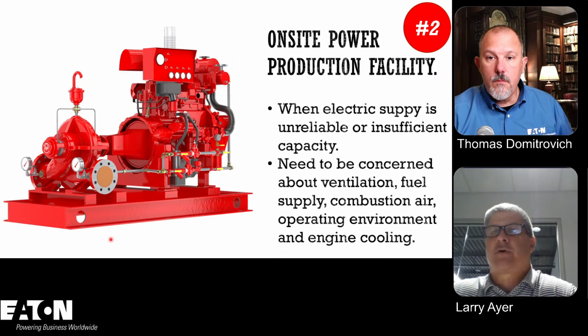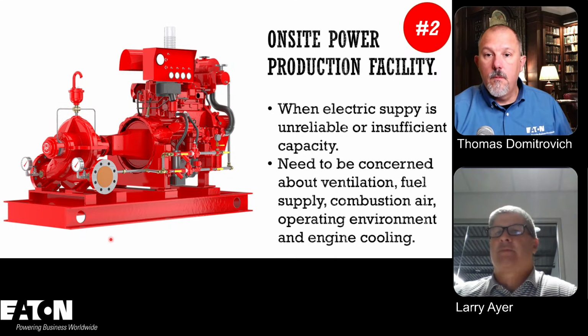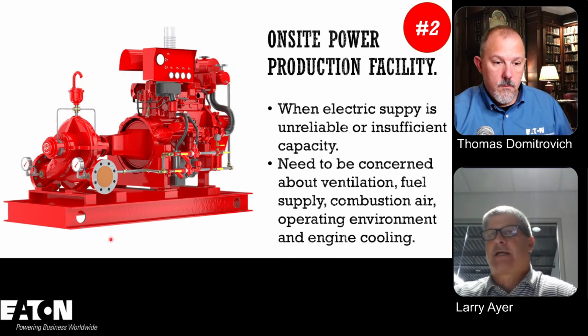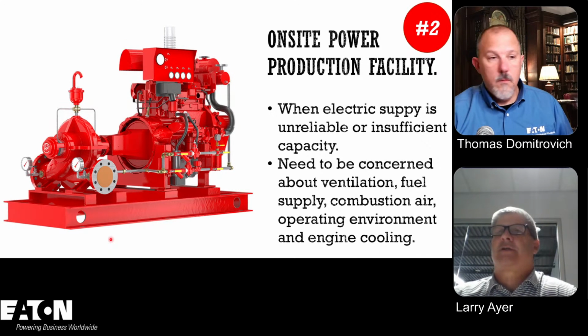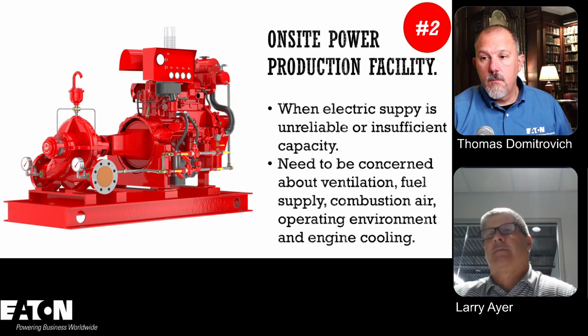You don't need to worry about whether you need another source of power, but you do need to be concerned about ventilation, fuel supply, and combustion air. Like I think Don said before, if it's outside, you've got extreme environments and things like that. It might not be the best choice. But that is another way you can wire a fire pump. That was number 2 on that list.